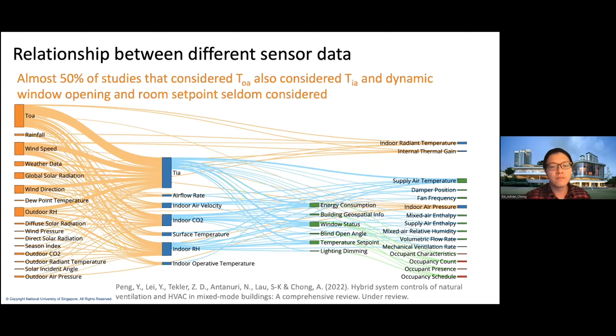Based on this, we started exploring. Since rule-based control doesn't work very well, we thought: how about learning-based solutions? We applied reinforcement learning on a virtual model of our test bed, exploring window opening from 0, 25, 50, 75, to 100%, and a cooling set point between 24 and 27 degrees Celsius at 1 degree steps. We found we were able to reduce cooling energy by more than 50%. That was very surprising.